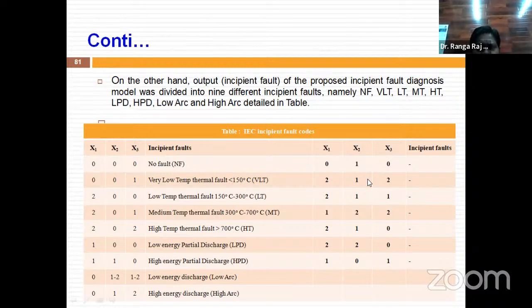The reason is there are multiple faults, not only one. There is a partial discharge fault, an arcing fault, a low temperature fault, mixing of faults - not only one fault. Single faults are defined by the standard methods, but multiple fault cases are not defined. So there is a problem in the conventional method.